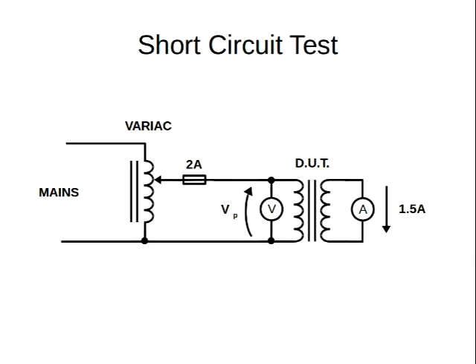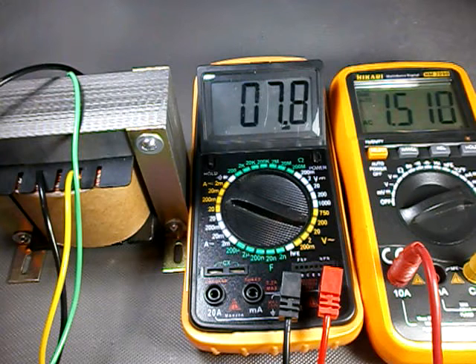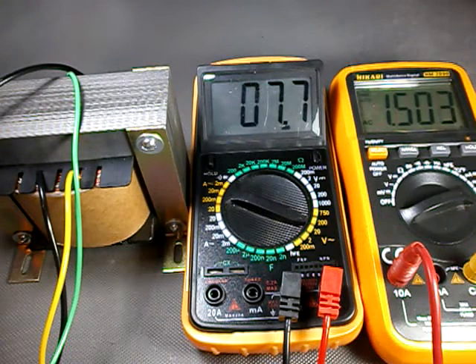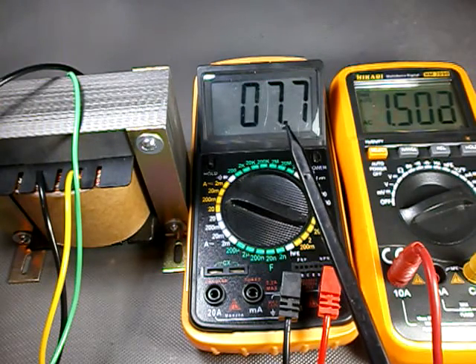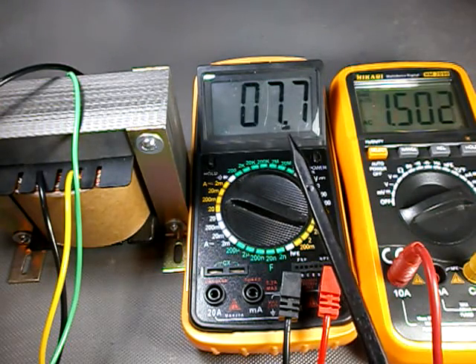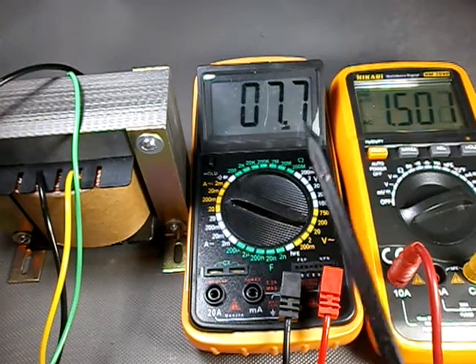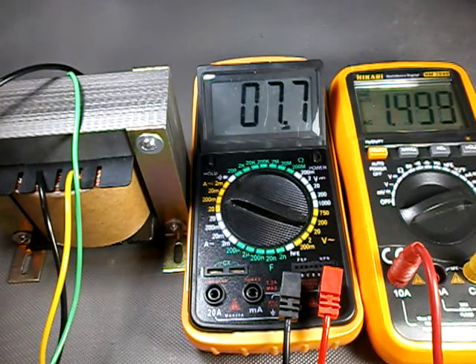Now it is time for the secondary short circuit test. The purpose here is to measure the voltage regulation. Using the variac we are supplying the primary a voltage which is enough to make the secondary exhibit a nominal current of 1.5 amps. We can see that we have 7.7 volts on the primary. Now the effect of R sub C and L sub M can be neglected, because the voltage on the primary is much less than the nominal voltage.